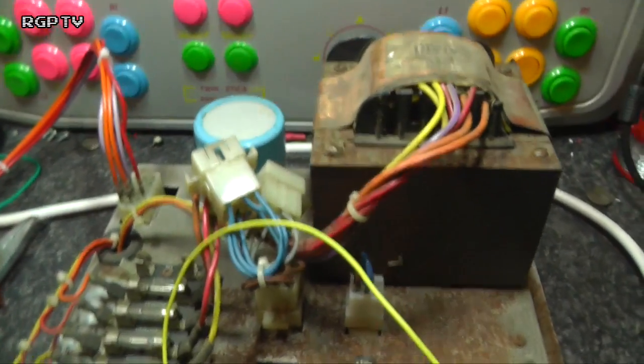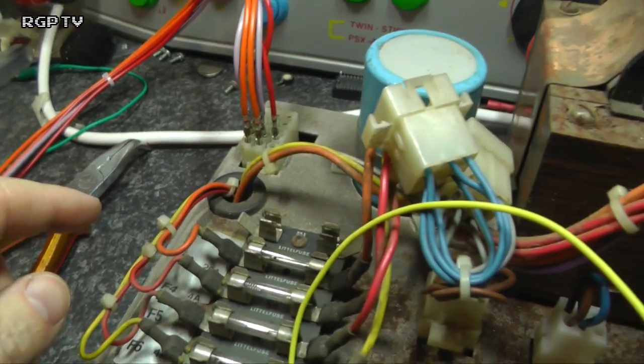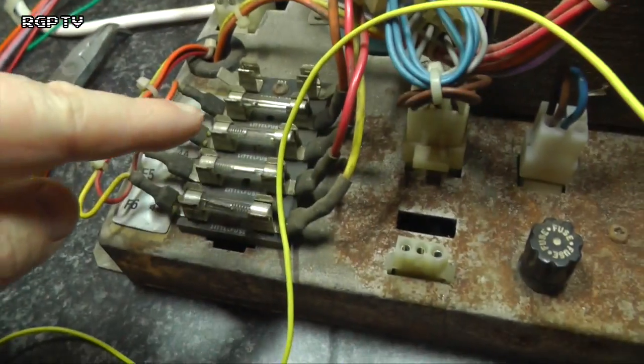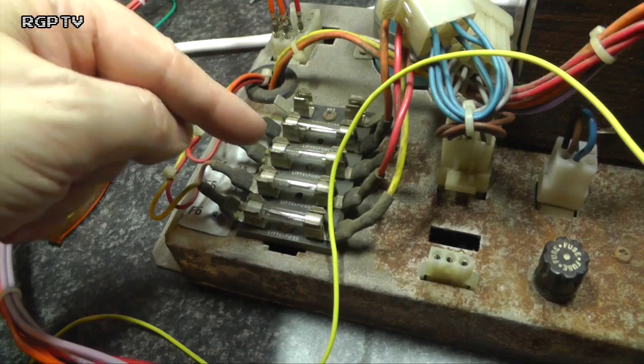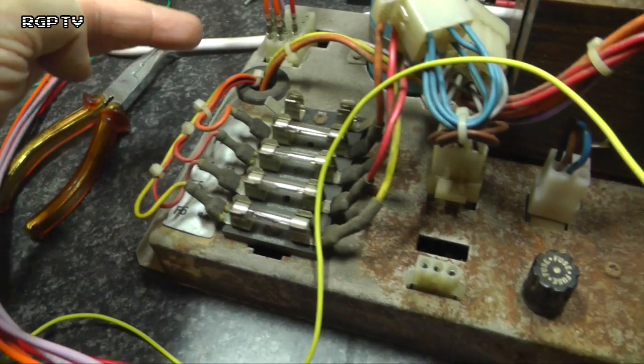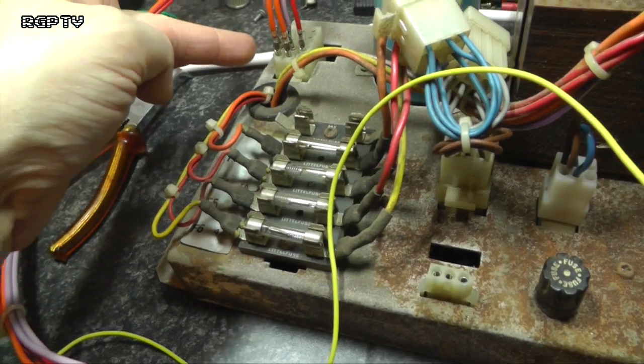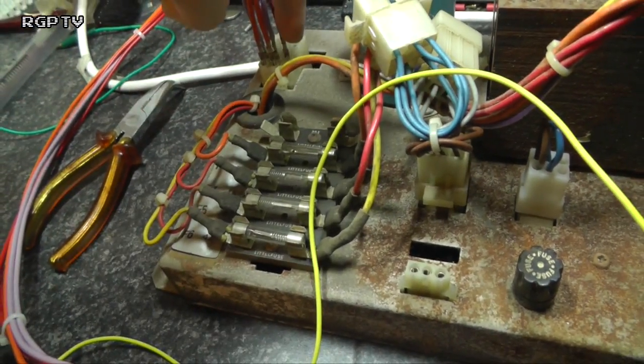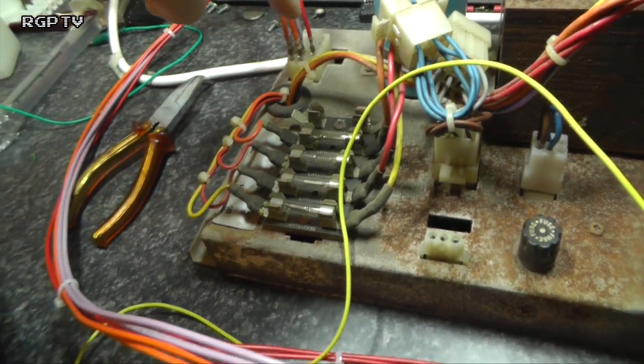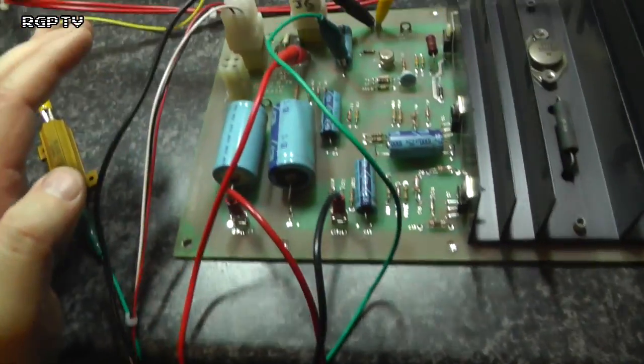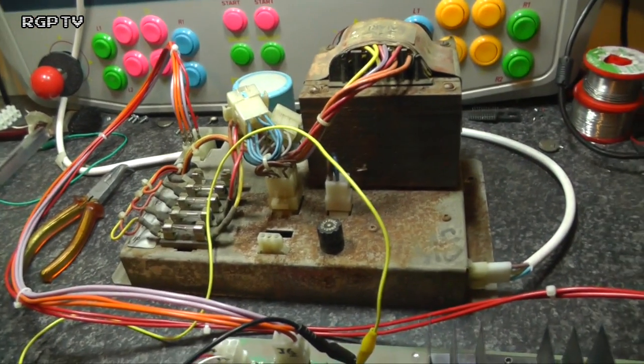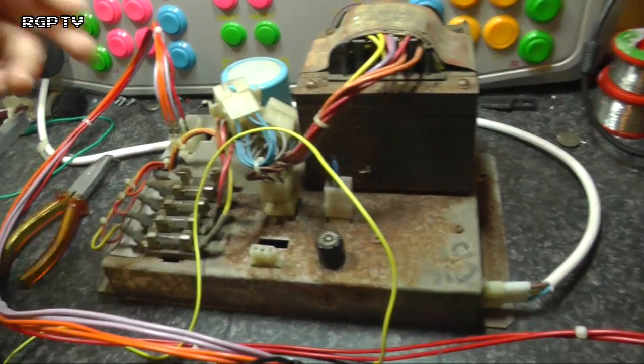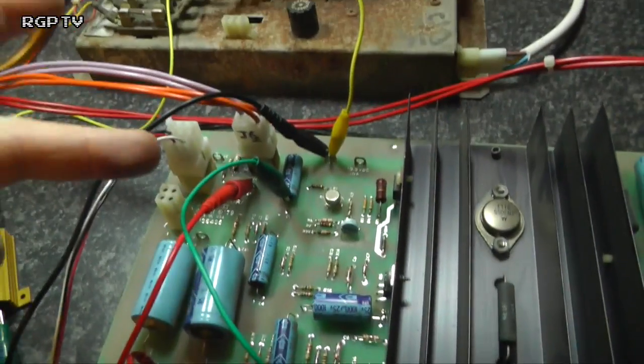Coming out from here through some fuses, usually F3 that you have problems with, we have 10.3 volts unregulated and 36 volts AC. I've hooked these two lines up, these are the only power inputs to the AR2.